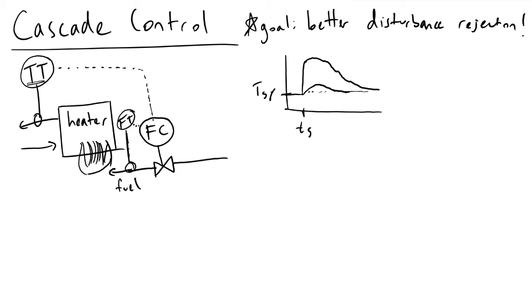In this case, a flow transmitter would be a very good investment from an engineering perspective if the flow rate of our fuel stream could be considered a disturbance, if it's not very constant with time. Monitoring it and making use of that information is critical.